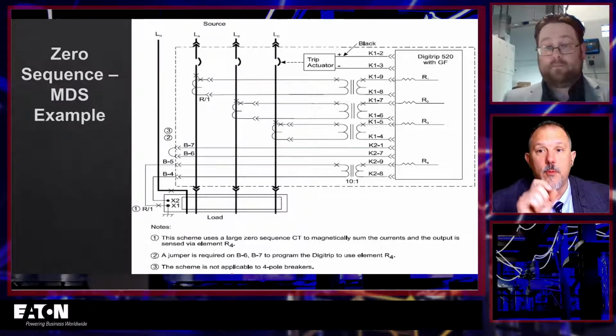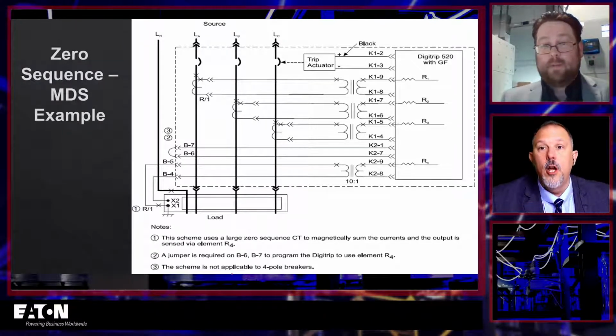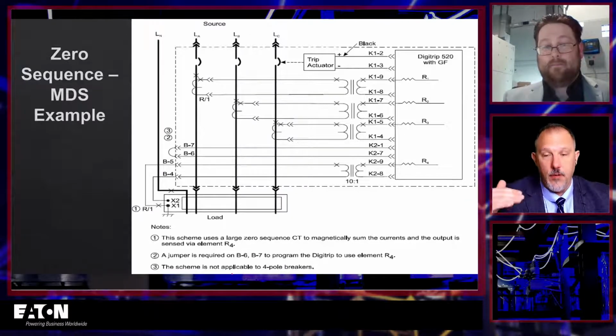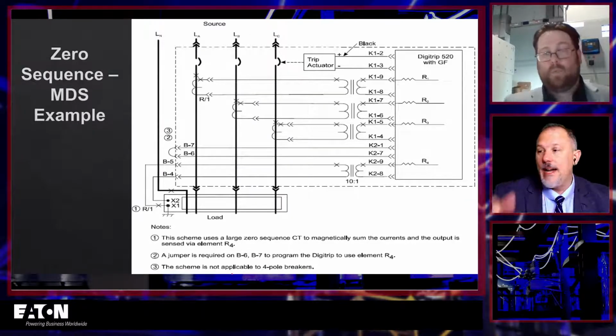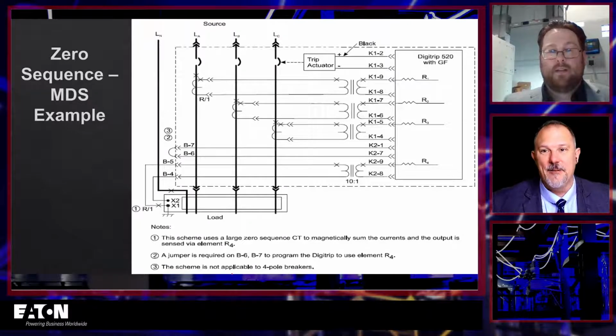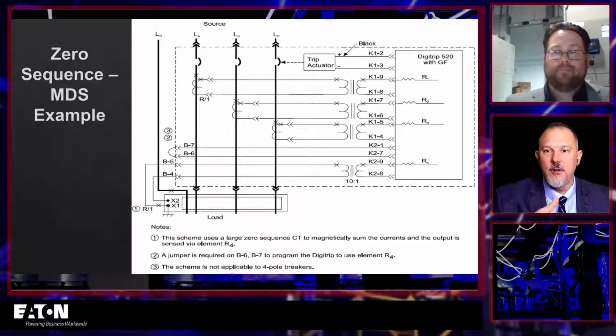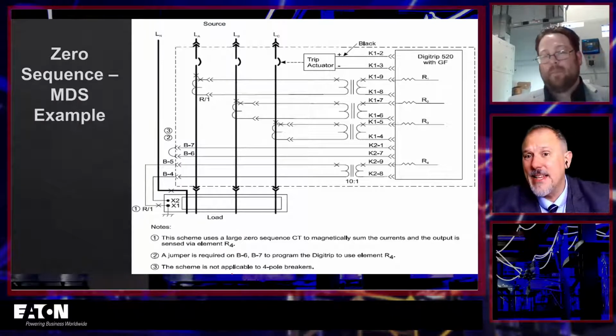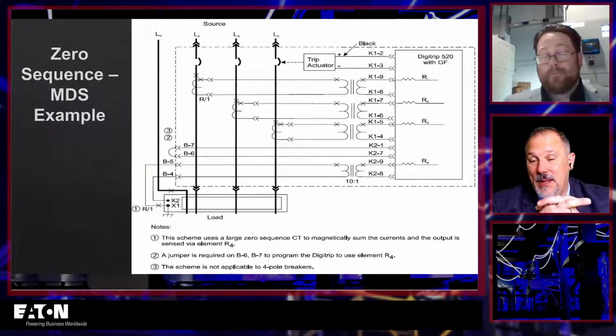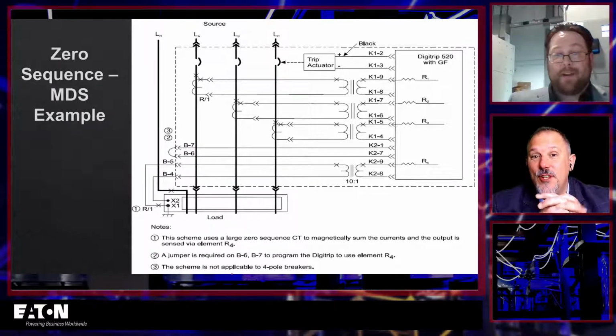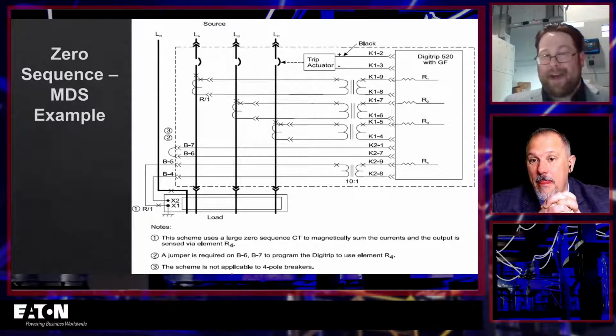But you make a good point with regard to saturation, knowing what the expected fault current value is, because if it's really high, which these zero sequence wouldn't be really high, right? It'll be a low number because it's not going to be like 20,000 amps. It'll be a smaller number because it'll be a differential. Okay. But I guess it could be pretty doggone high, couldn't it? It could be, depending on where you are in the system, right? That's true. That's where it matters.